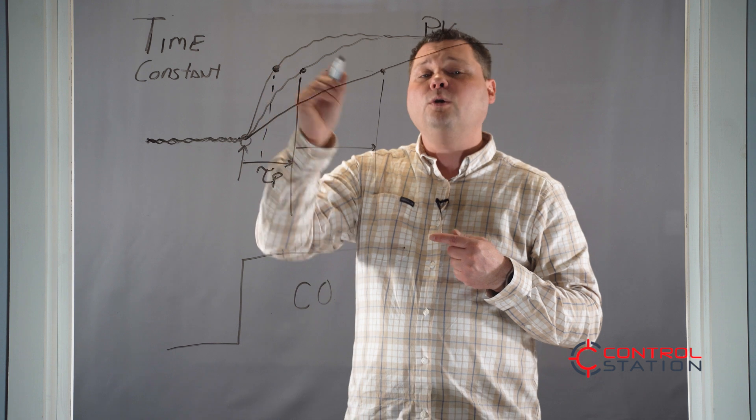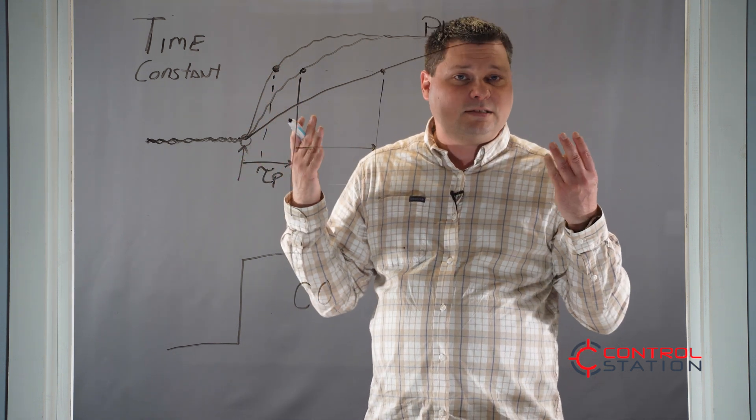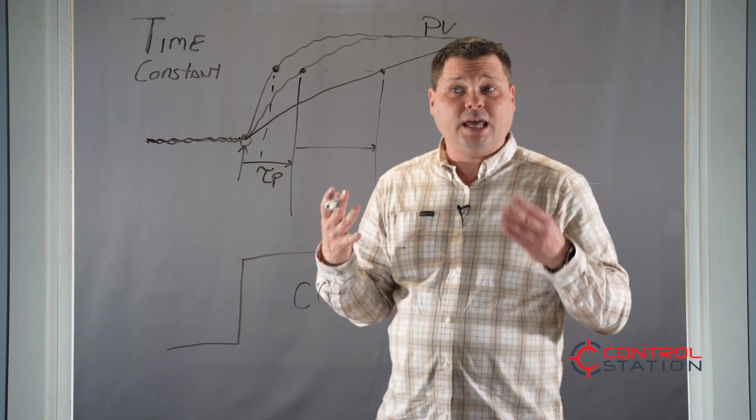You can't have a flow loop that has a one second process time constant execute every 10 seconds. You're going to miss a lot of the dynamics and your control will not be very stable.